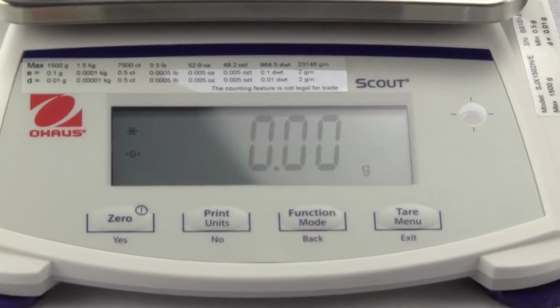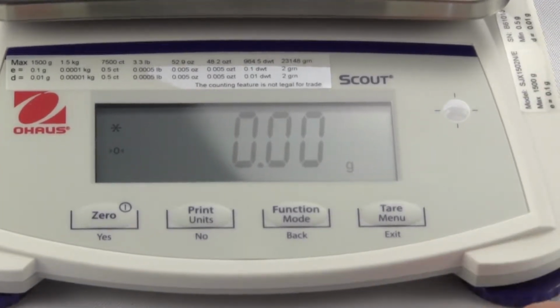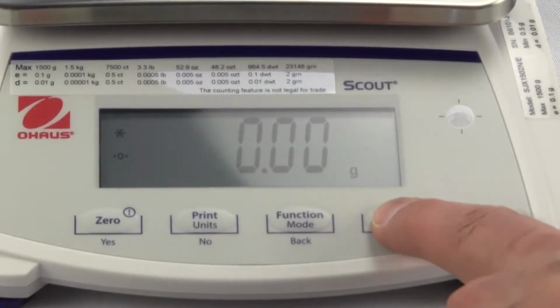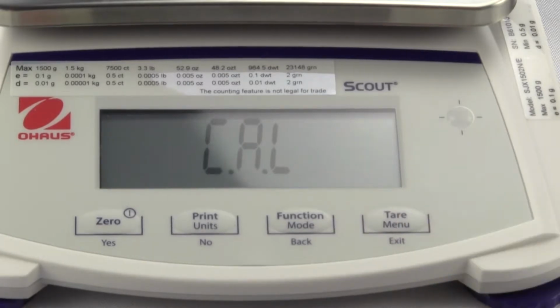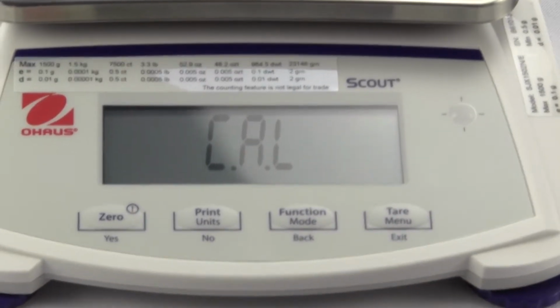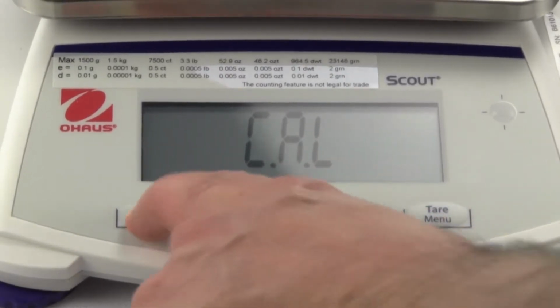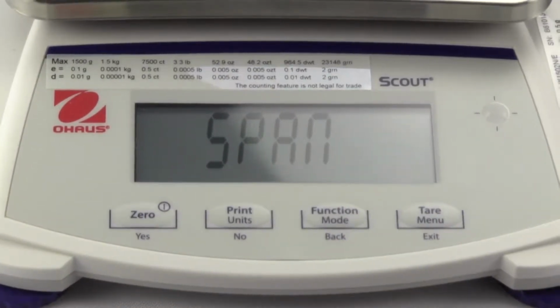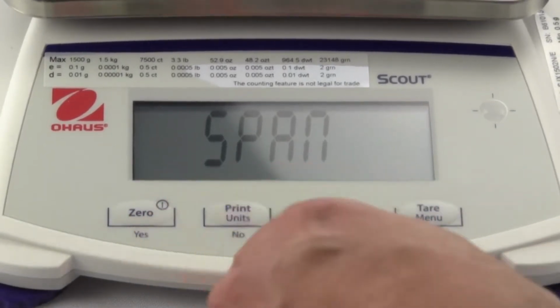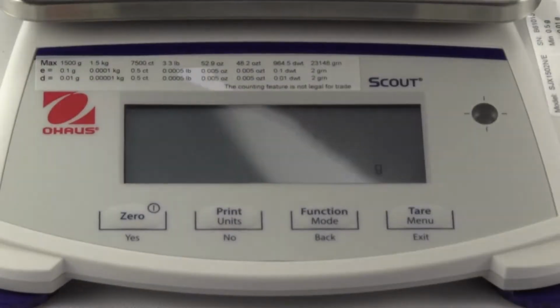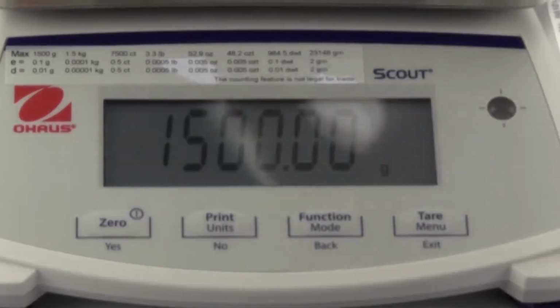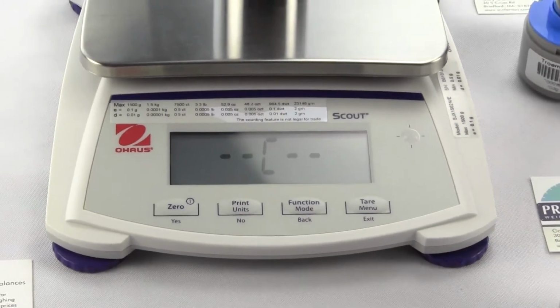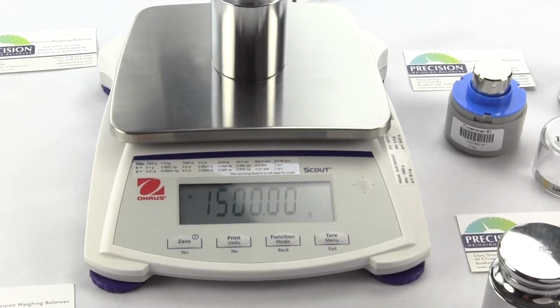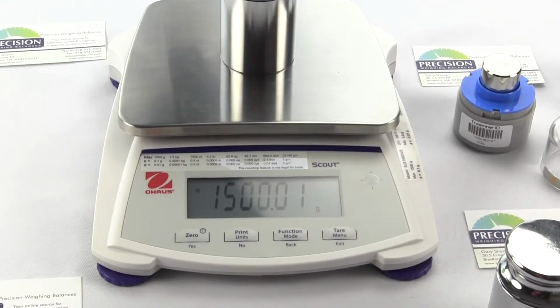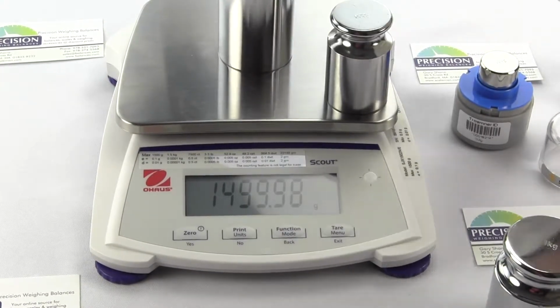Now to do calibration, the first thing you want to do is press and hold the menu key until you see menu. Then release and it will show cal. Press yes, and you have span calibration. We want to do a span calibration, so we'll hit yes again. The default out of the box is 1,500 grams. So we need 1,500 grams. You want to put them on the center of the platform. The scale automatically will take the read, and it says done, and then it returns back to the weigh mode. So that's how you do a span calibration.